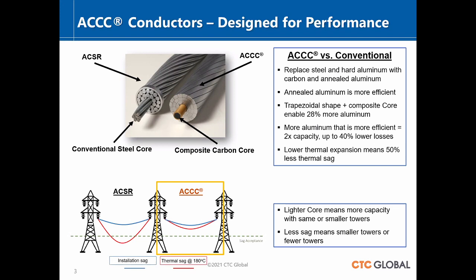In this, we were describing the classical, most commonly installed conductor, the ACSR, aluminum conductor, steel reinforced. We were describing that as being the steel core with round wire that carries the electricity. Then we began to describe the conductor that has the carbon composite core. We replaced the steel. It's lighter, stronger, and as you put current through these lines, they heat up, and steel will expand. If you've attached it to 2 points, like in a tower, then it's going to sag.